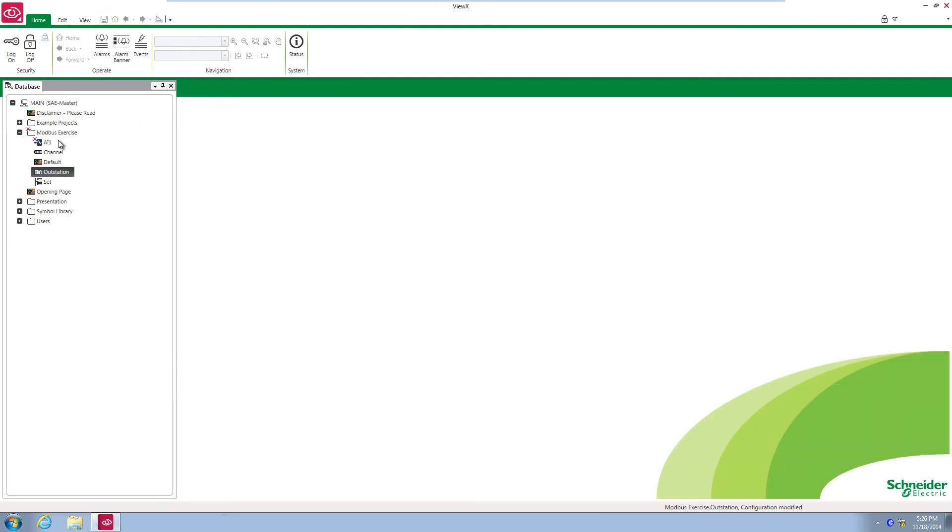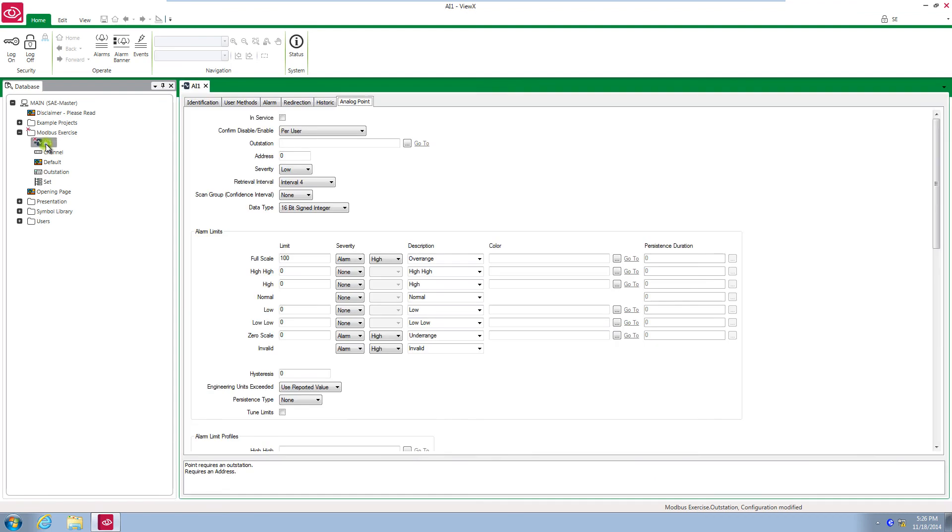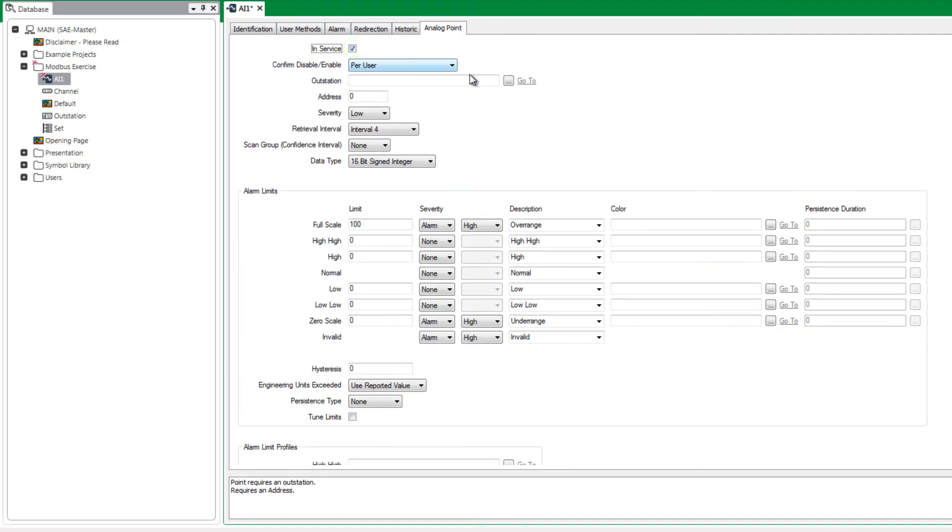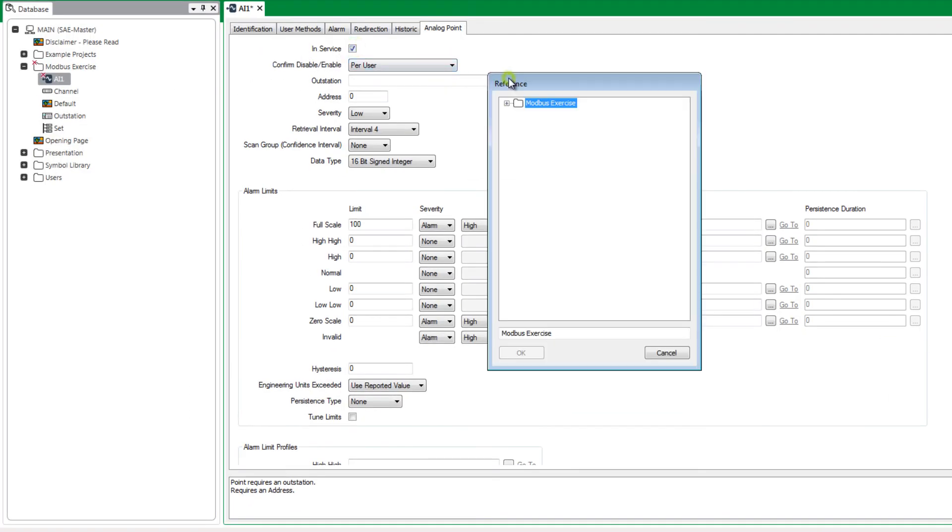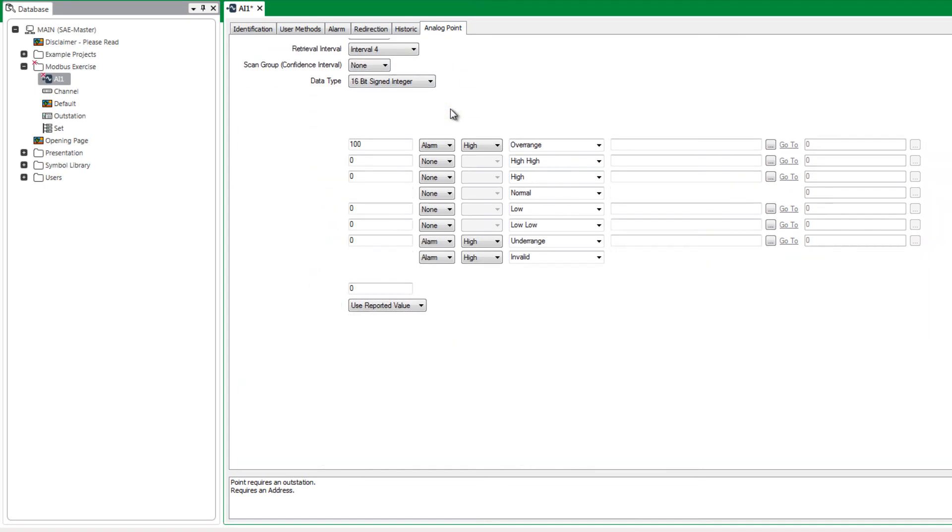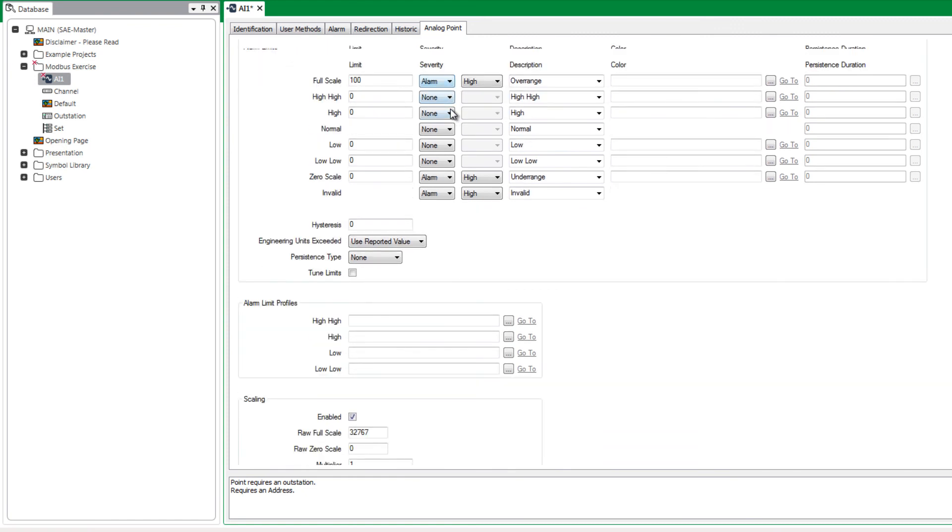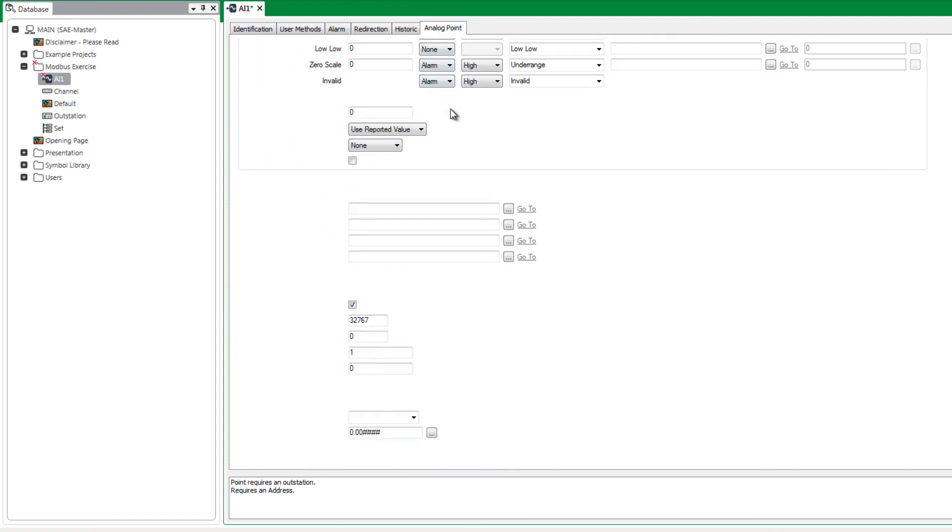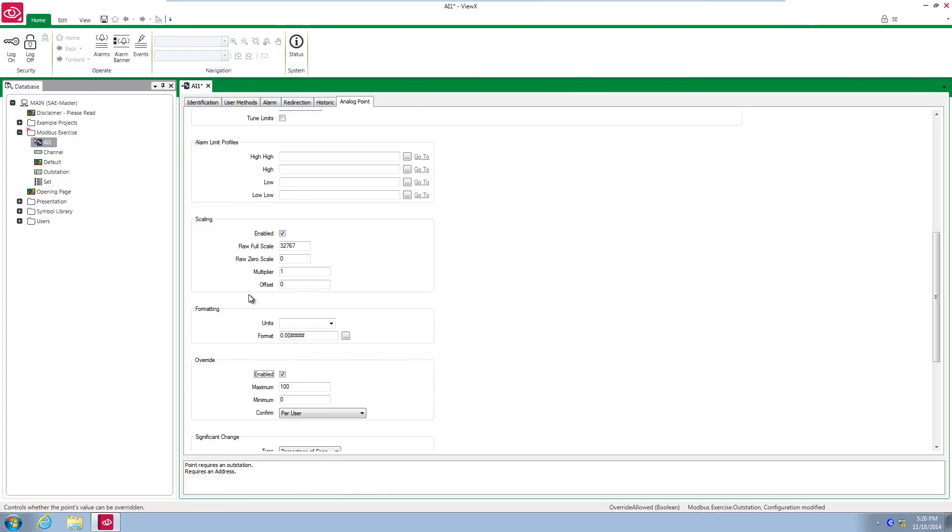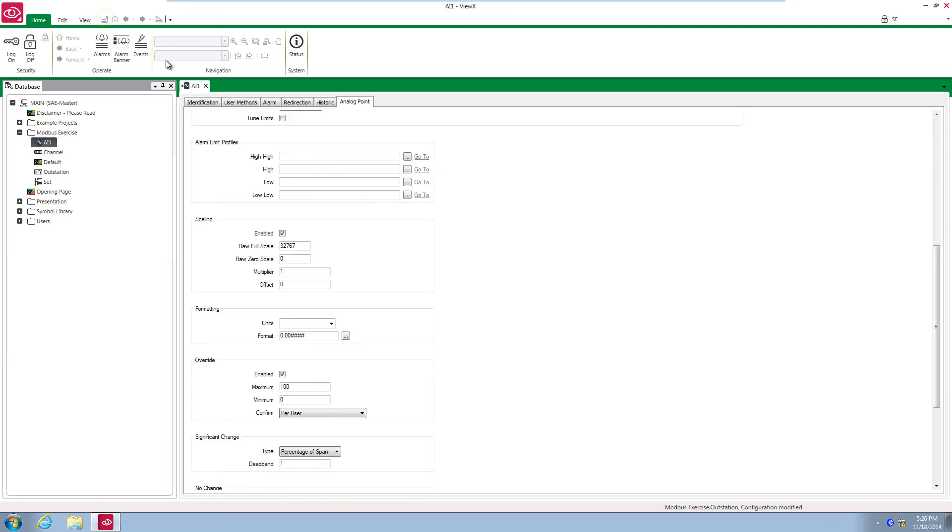Open the AI1 object. Go to the analog point tab and put it in service. Hit the browse button next to the outstation field and browse to the outstation object. Set the Modbus address to 3001. Scroll down to the override option and enable this. This is purely to demonstrate the functionality of the Modbus point without being connected to a physical PLC. Save and close the object configuration form.